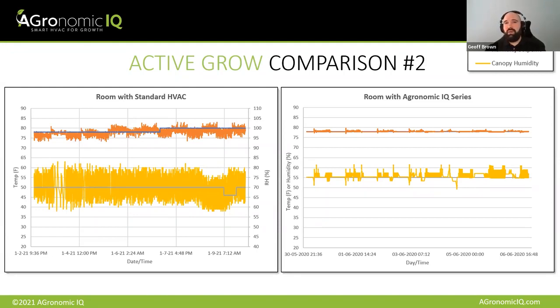This also has an energy impact to your facility. So when you're banging stuff on and off, which is ultimately what's happening here, you've got a standalone dehumidifier or a packaged air conditioner that says, okay, my room's too hot, I'm going to turn on 100%. I'm going to drag the room down until I'm at my low dead band set point. I'm going to turn off. I'm going to wait for the room to heat back up and rinse, repeat. There's no modulation and control there. And so not only is your room environment not that stable, but it's also an energy pig as a result.